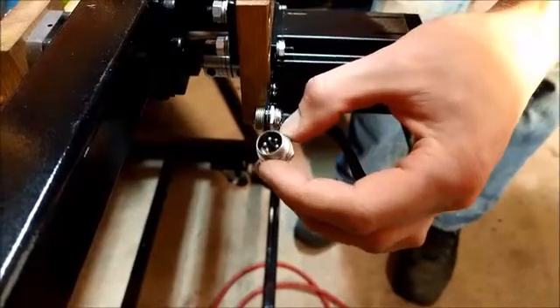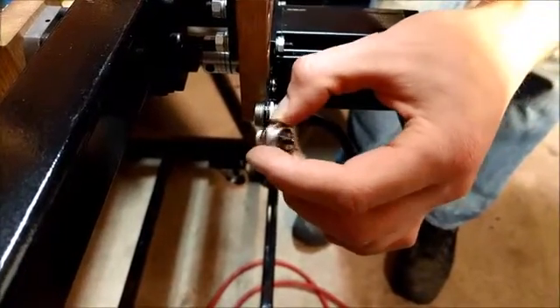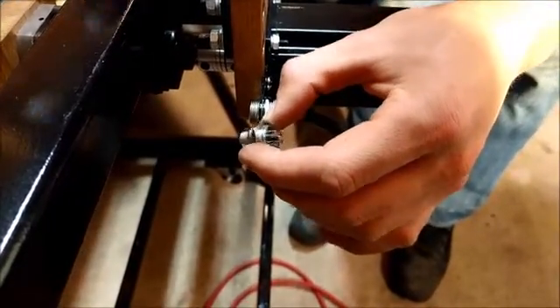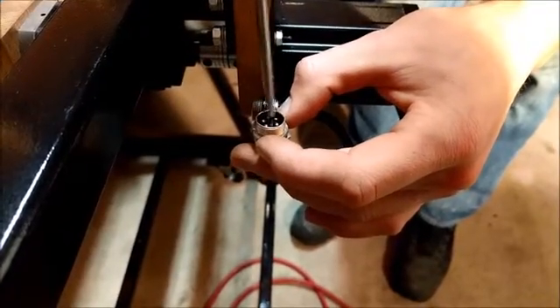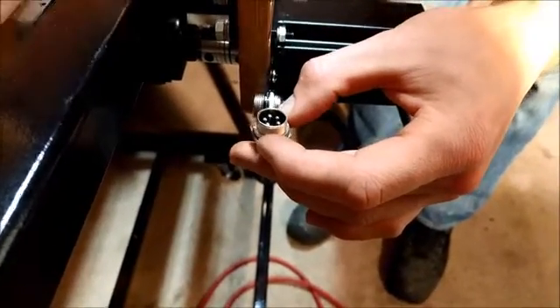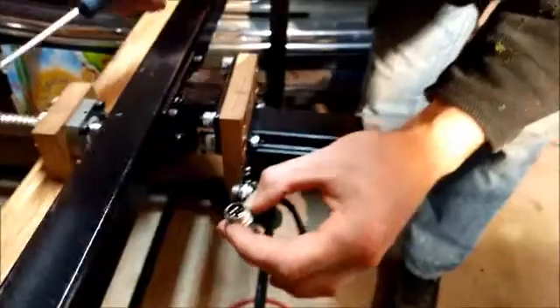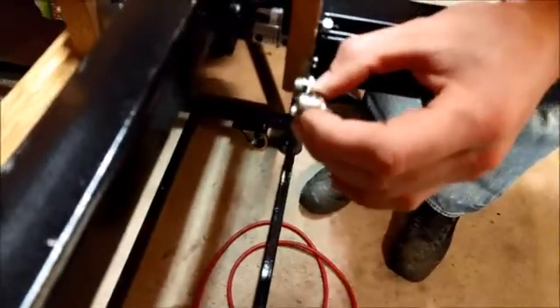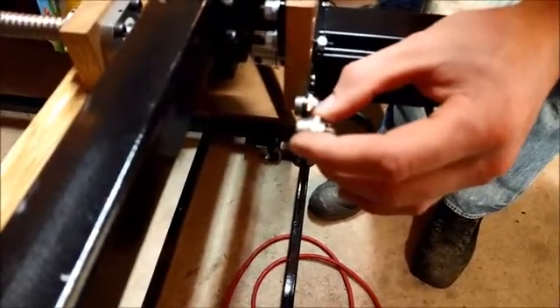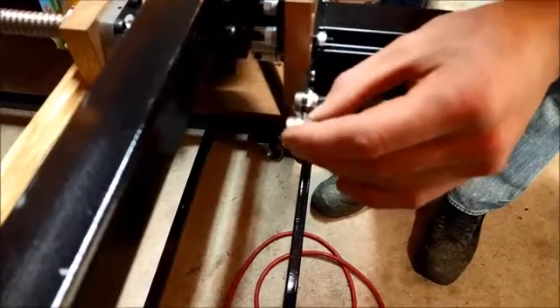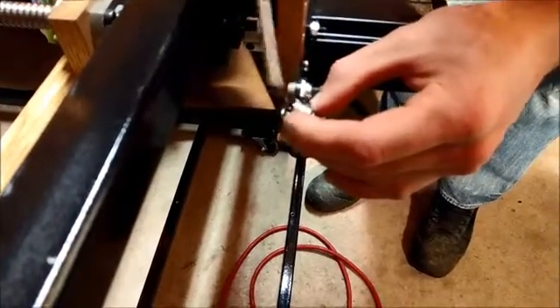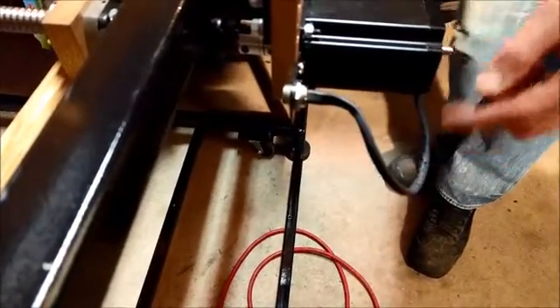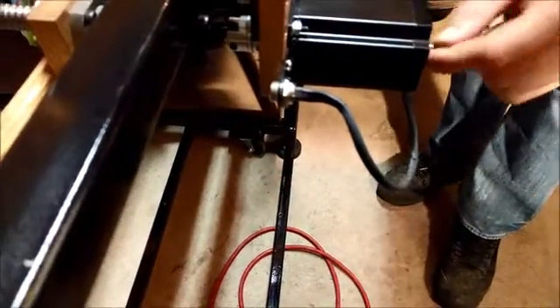And with these plugs, you want them coming in horizontally. You do not want them up like this or turned like that, because when you're cutting, first thing that's gonna happen, that's gonna fill with metal, you're gonna have problems. That's gonna fill with wood, you're gonna have problems. So you always mount plugs or anything—limit switches, anything to do with a plug—is always horizontal so nothing falls in there.